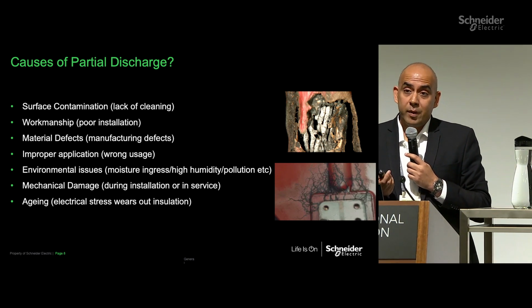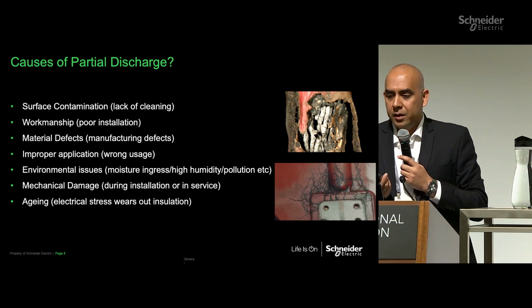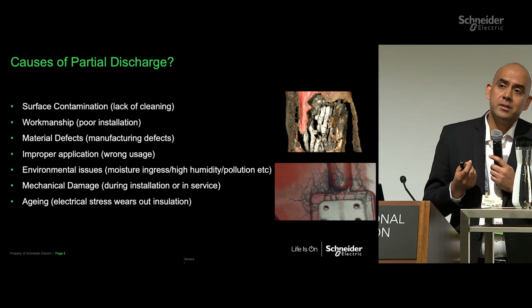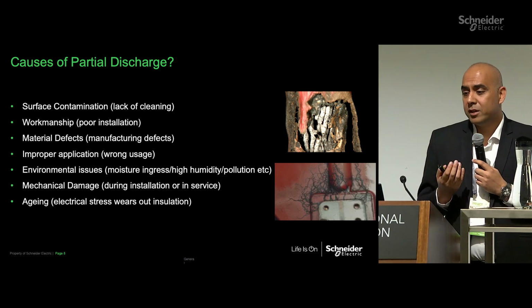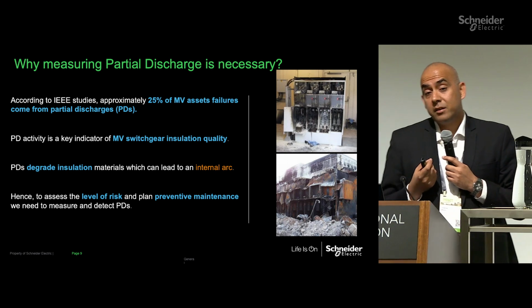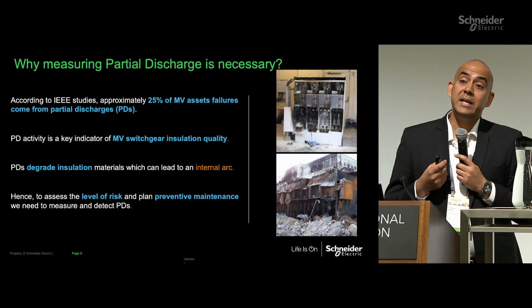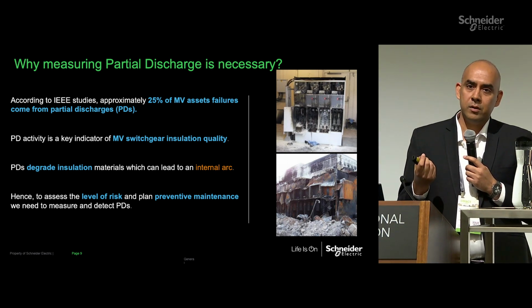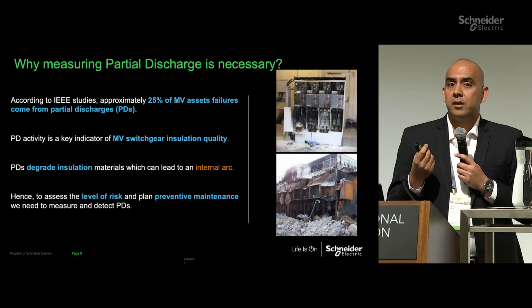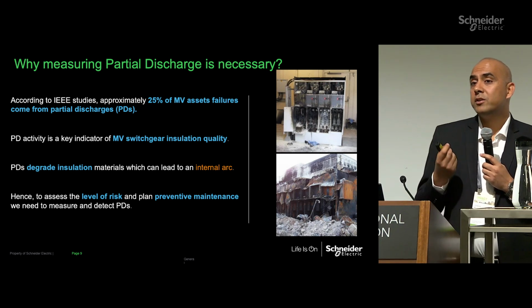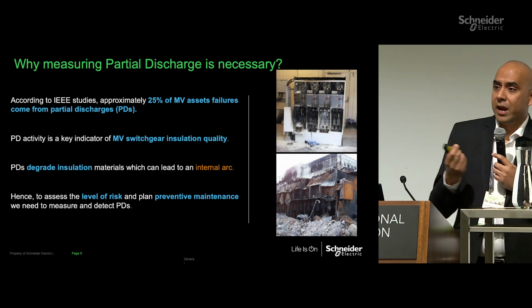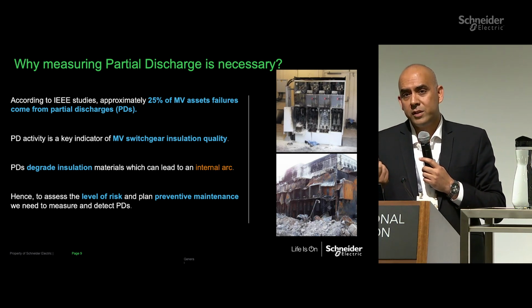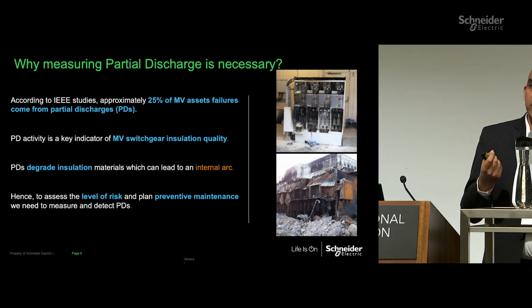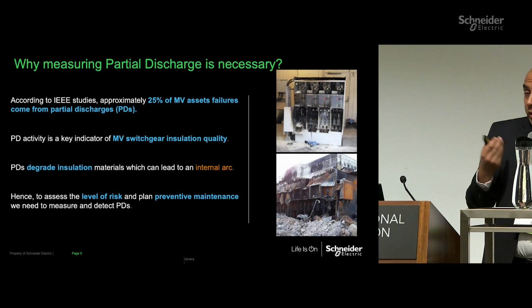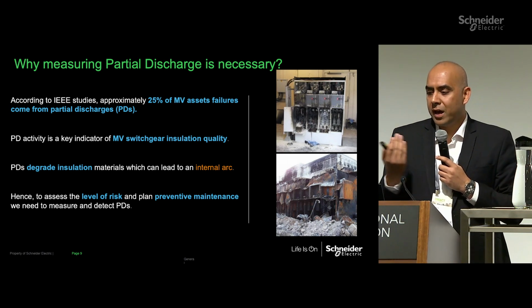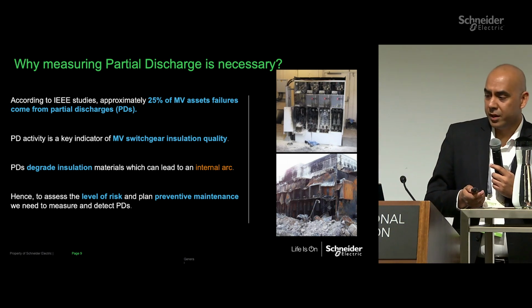And that's why monitoring of partial discharge becomes very, very critical. So what happens is, of course, we have heard about the failures, but partial discharge activity is a sign of aging, and it degrades the insulation as it goes on. So if it doesn't get monitored, the insulation can degrade very gradually and cause failures. So it's important to assess the risk which our systems have. It could be through periodic checking or through continuous monitoring. You can have these checks to avoid these issues coming in.